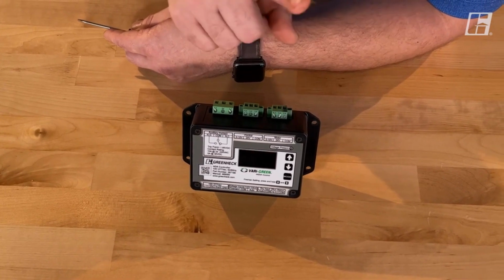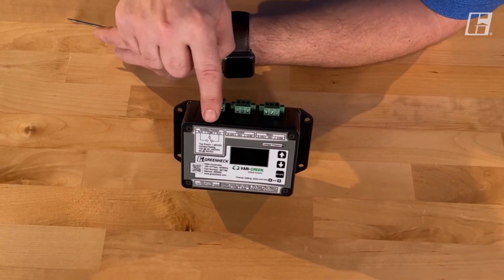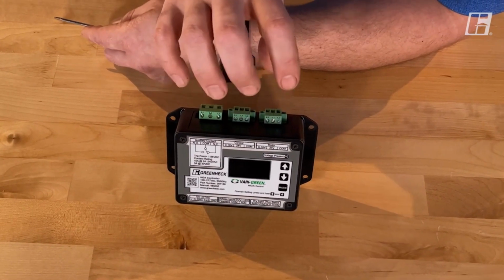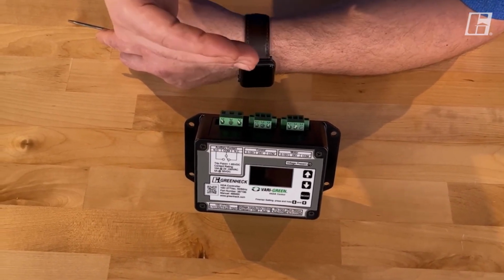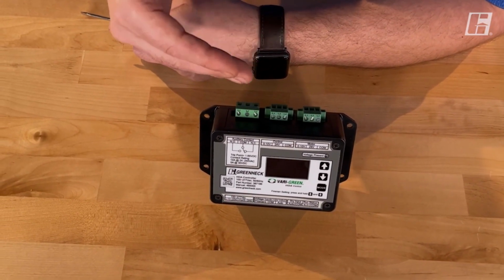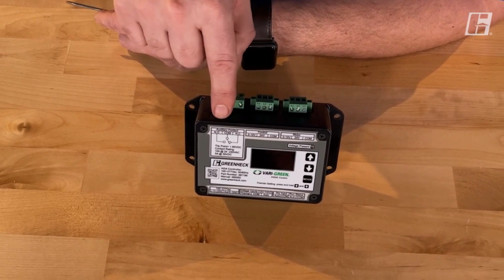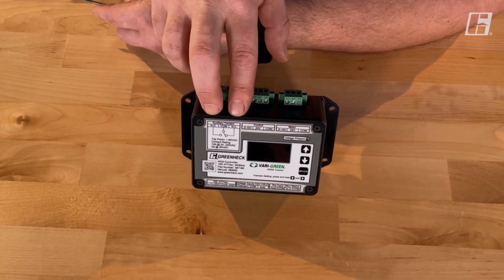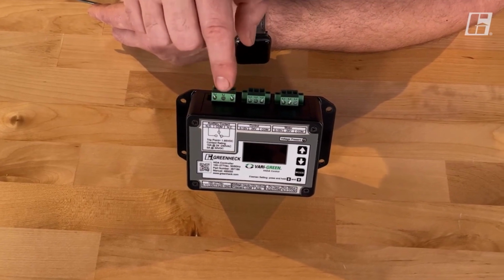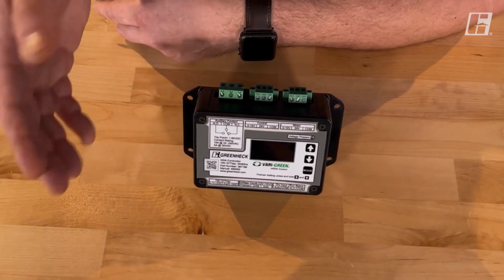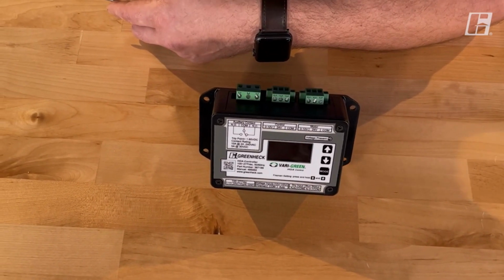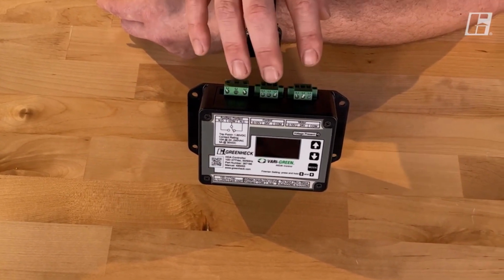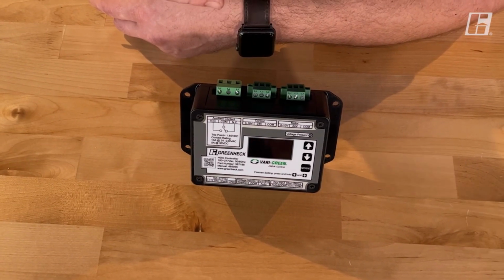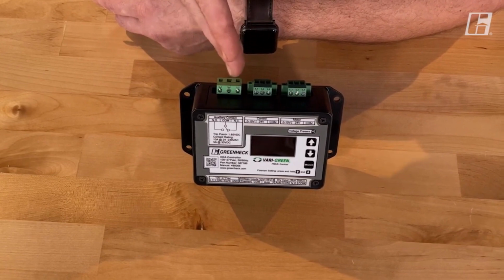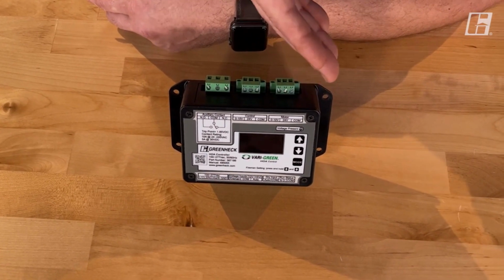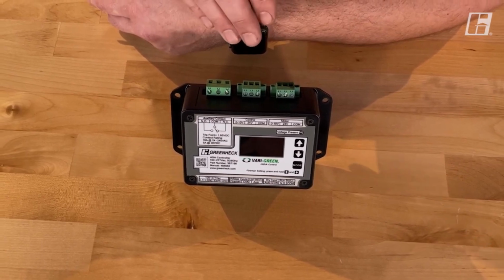One more terminal across the top, and that's the auxiliary contact. Anytime this control sees a run command, a 2 volt or better signal, this will change states. There's a common in the middle with a normally open and a normally closed terminal. This is most traditionally used to bring power by others into it and then pass it to a damper actuator when the motor is running. So you tell the fan to run, this changes state, power is passed to the damper actuator, it opens, and then the soft start of the Vari-Green motor brings the fan up to speed.